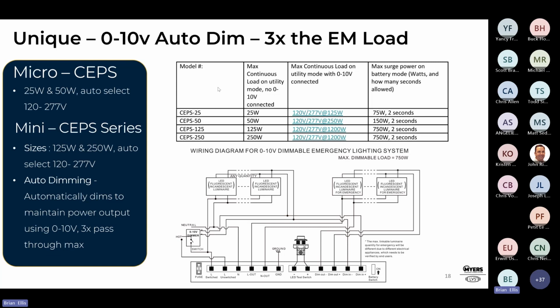But if you're dimming it, and it's only available in 0 to 10, right? If you're utilizing 0 to 10, which is most of our applications today, why not dim that load so that we can get more bang for our buck out of the product? So think about putting a 750 watt load, right, and utilizing a CEPS-250 and connecting the 0 to 10 to your emergency fixtures. What happens is, under normal circumstances, this control device in the bottom left is allowing it to turn on and off with this switched input. You also feed it with the unswitched input so that it knows when utility is gone, and it also allows this to feed through the inverter under normal circumstances.